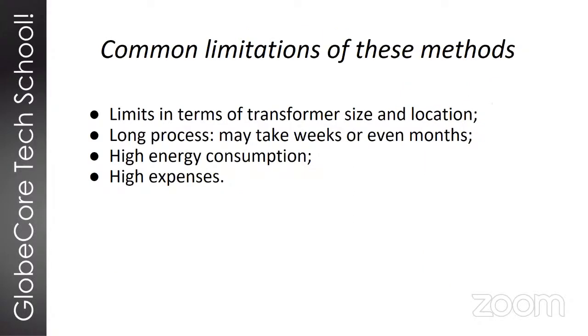So to summarize the things we've talked about, all of these methods are usable in practice. However, none of them is completely universal, none of them is an all-in-one solution. Some are limited by size, some are limited by the location, because some cannot be used in the field. So one good method that we think is good for preventive reduction of moisture in the transformer when it is running and operating is the continuous drying using a sorbent.